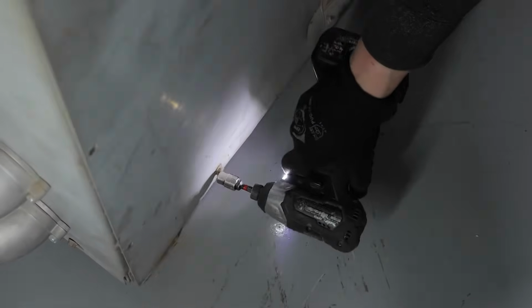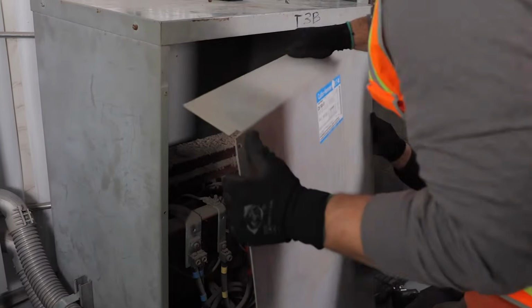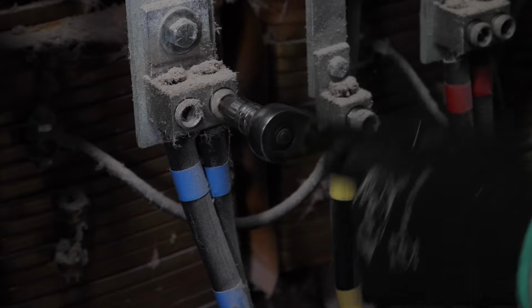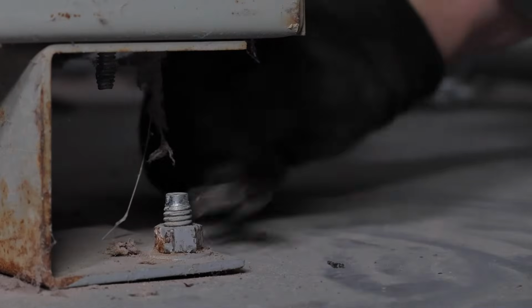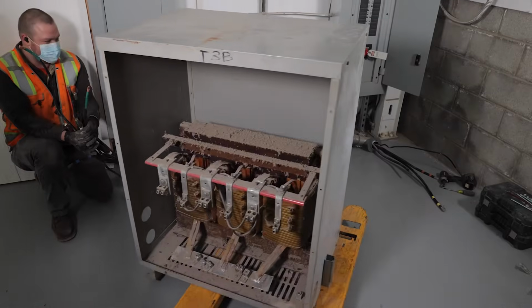The front panel of the existing transformer is removed and all wires are disconnected. First, the primary side is disconnected, then the secondary, and all ground wires. The transformer is then unbolted from floor anchors and removed.